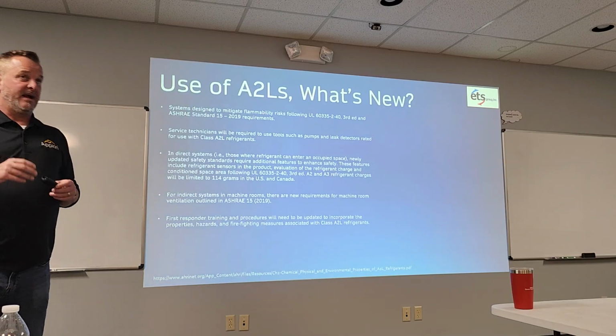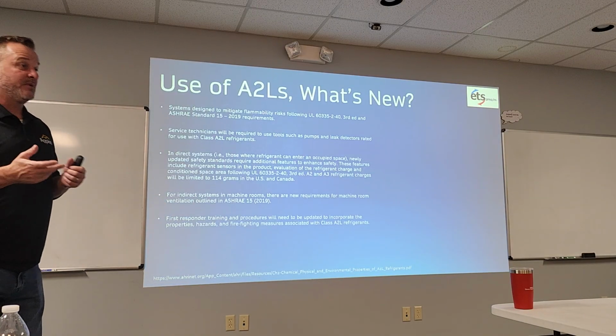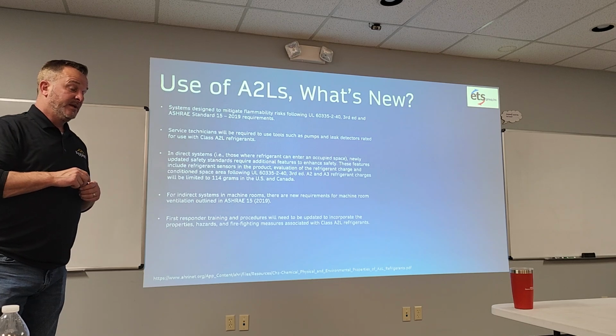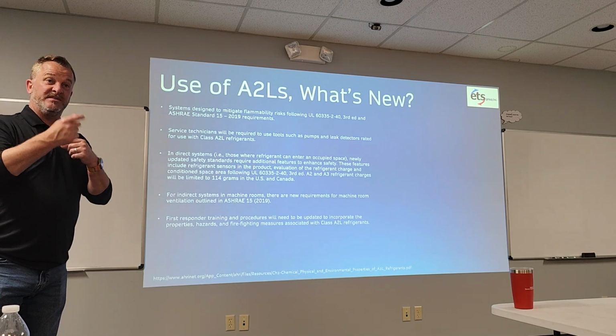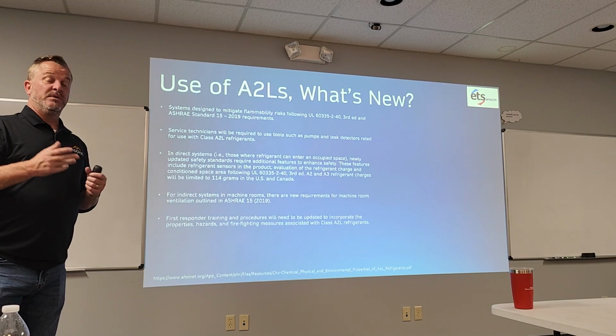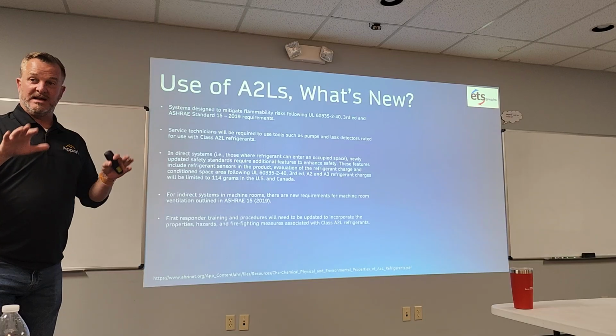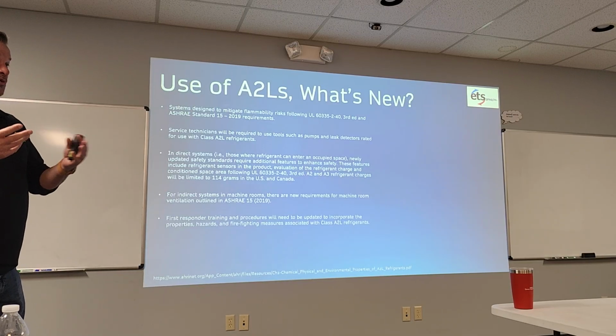A2 and A3 refrigerant charges will be limited to 114 grams in the US and Canada. So your A3 refrigerants, like propane and butane, you can only use so many ounces inside a sealed system. One of the big brands, True, has great videos on this that put a lot of people at ease. You guys familiar with the True brand? Your coolers and commercial equipment.